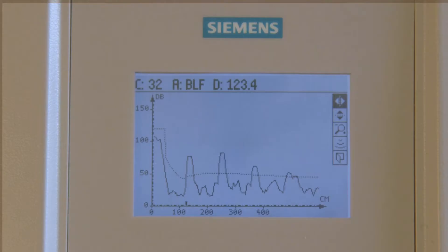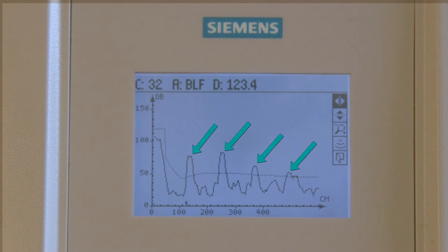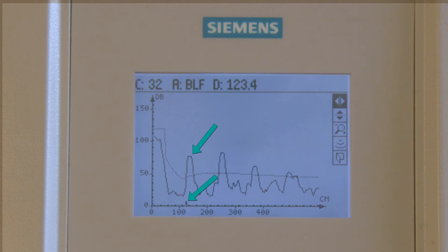An echo profile is a digital representation of the inside of a vessel or tank. It consists of a scale for amplitude, a scale for distance, an echo profile, the time-varying threshold — also called a TVT line — and an echo marker. If the echo is above the TVT line, the echo could be detected as the level of the material. The echo marker indicates the echo that the device has processed as the material level.